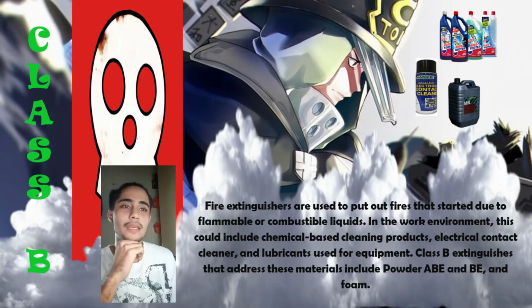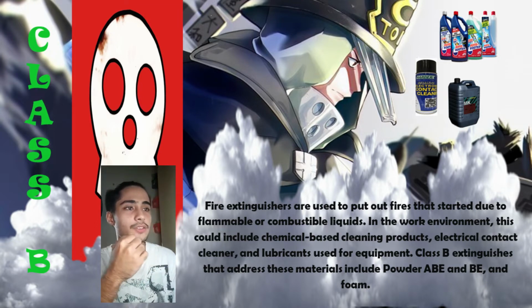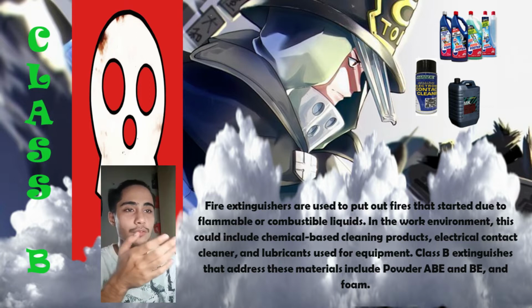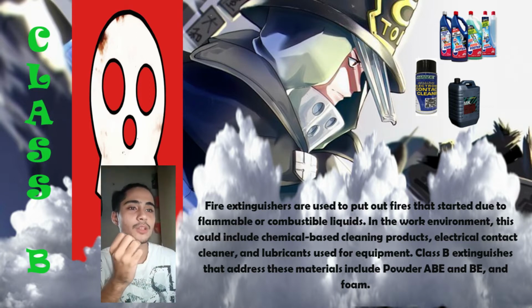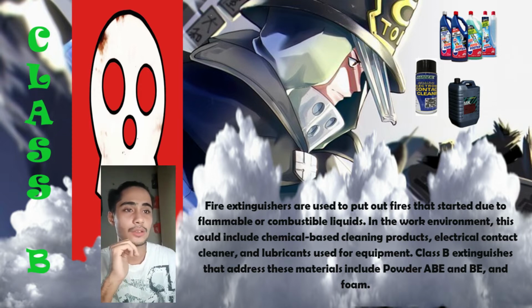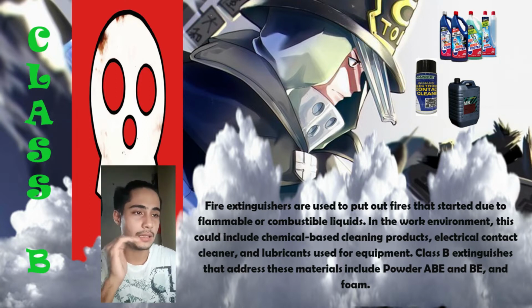In Class B, fire extinguishers are used to put out fires that started due to flammable or combustible liquids. In the work environment, this could include chemical-based cleaning products, electrical contact cleaner, and lubricant used for equipment. Class B extinguishers that address this material include powder ABE and BE and foam.